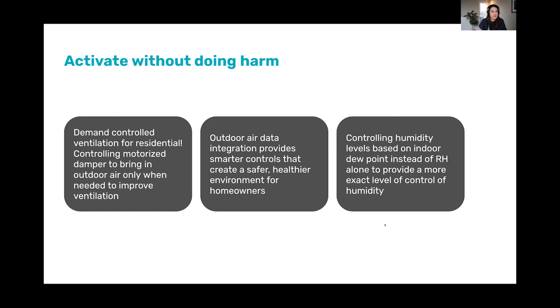And then also making sure of this, which is one of building science and high performance professionals' beefs with humidity control: a lot of humidistats are still controlling based on relative humidity. And like it's in the name, it's a relative parameter that isn't as reliable as something more absolute that indicates when condensation would actually be produced. So dew point is that parameter where we can have a much more exact level of control over humidity levels. So we want to get that solution equipment involved in solving the problems, but not at the expense of other levels inside the home.